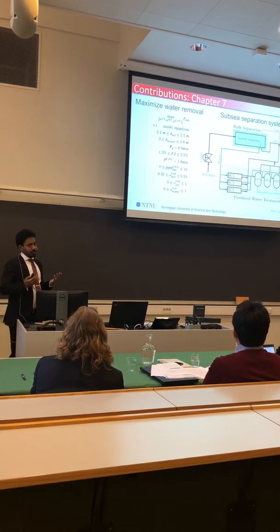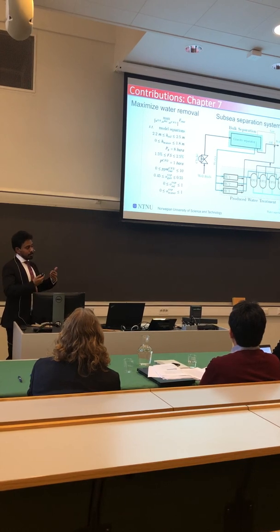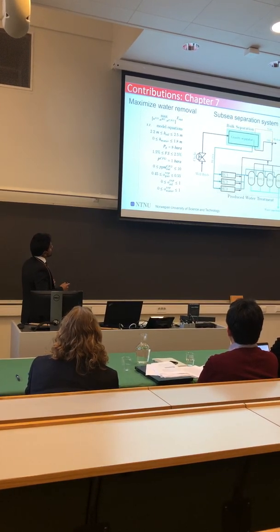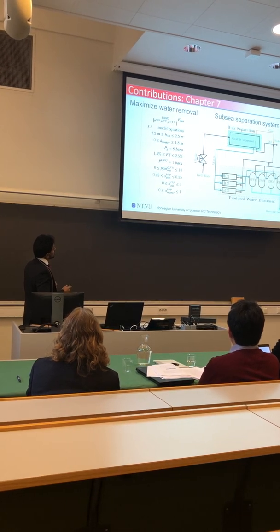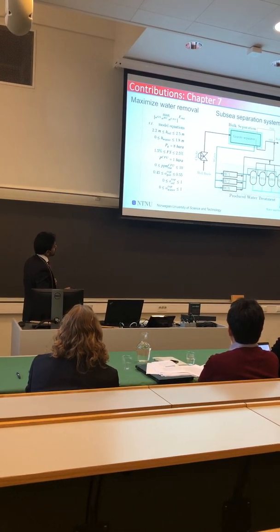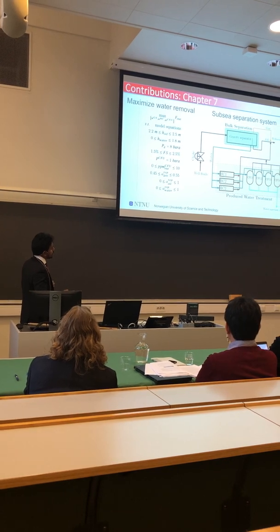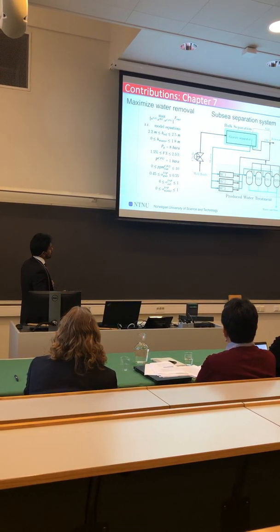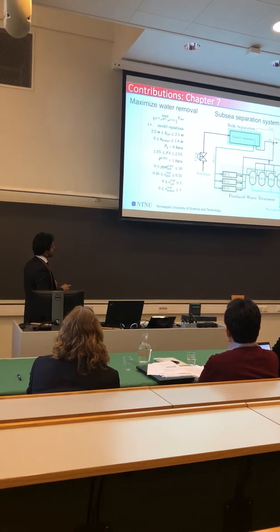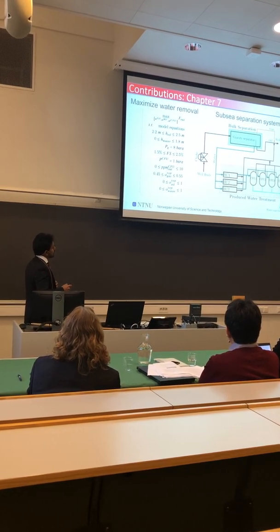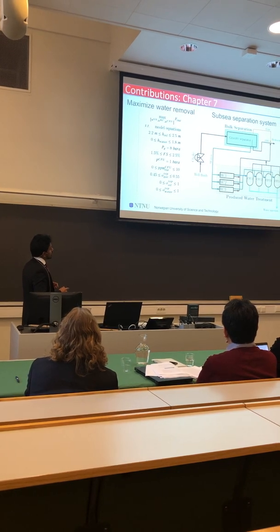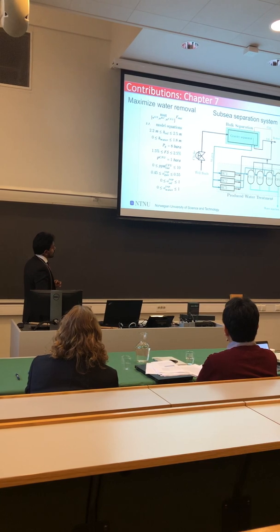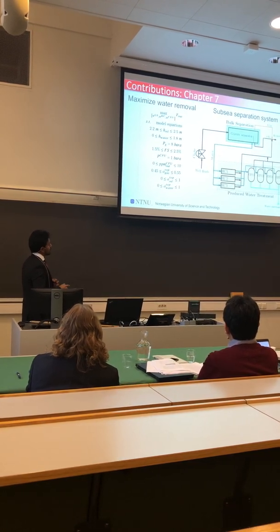Our model cannot describe the situation where the water level could go beyond the weir height. Gas pressure is fixed at 8 bar. The flow split in the hydrocyclone, where how much we take out in the central part, is between 1.5% and 2.5% of the inflow. The CFU is considered to be maintained at 1 bar pressure. The ppm of water that is going out here is considered to be between 0 and 10 ppm.